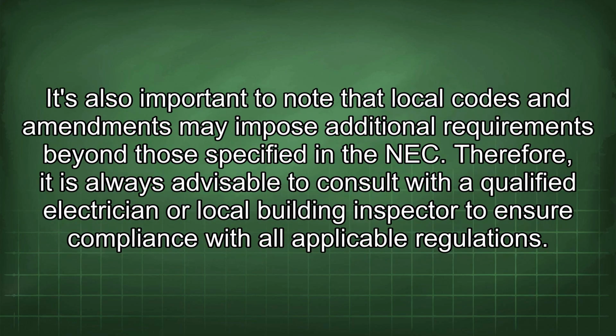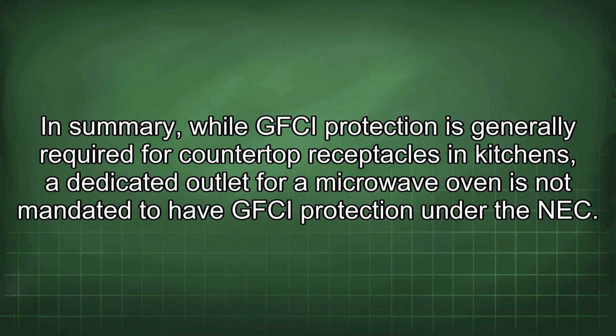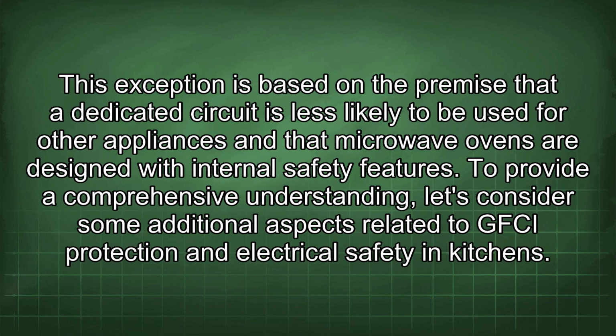It's also important to note that local codes and amendments may impose additional requirements beyond those specified in the NEC. Therefore, it is always advisable to consult with a qualified electrician or local building inspector to ensure compliance with all applicable regulations. In summary, while GFCI protection is generally required for countertop receptacles in kitchens, a dedicated outlet for a microwave oven is not mandated to have GFCI protection under the NEC. This exception is based on the premise that a dedicated circuit is less likely to be used for other appliances and that microwave ovens are designed with internal safety features.